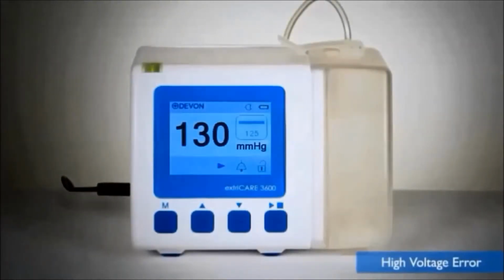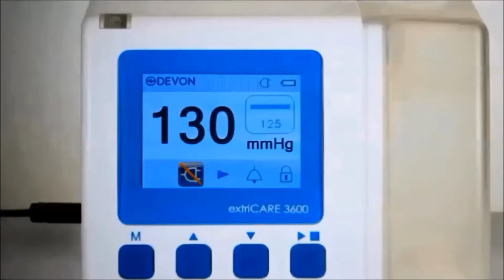The high voltage error alarm will sound when there is a risk of voltage incompatibility. During operation, if the input voltage is greater than 16 volts when the device is being used with an adapter that is not recommended, the LED light will flash yellow and the adapter error symbol will appear on screen until the correct adapter is used. Failure to use the correct adapter may cause the fuse to blow out.